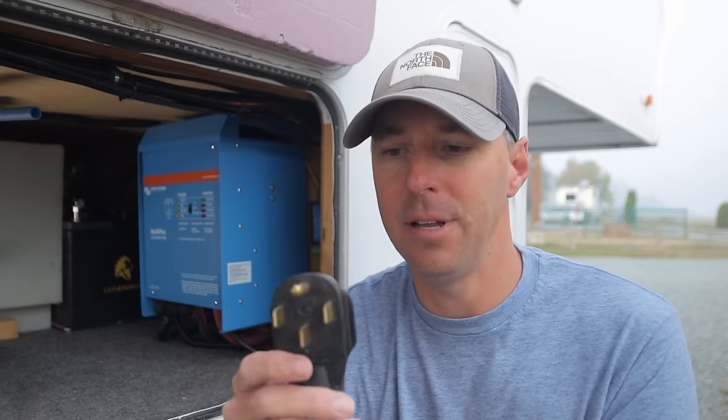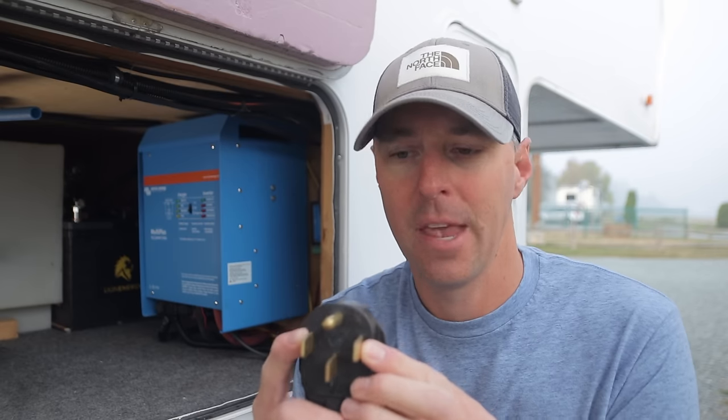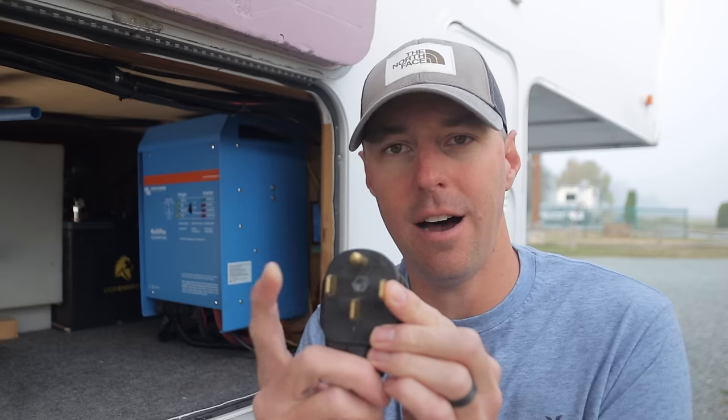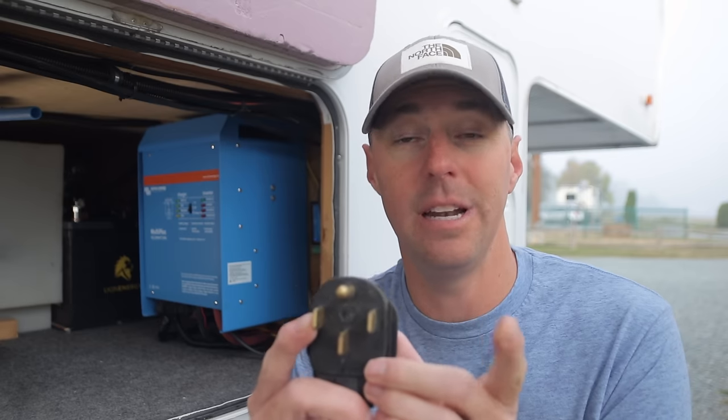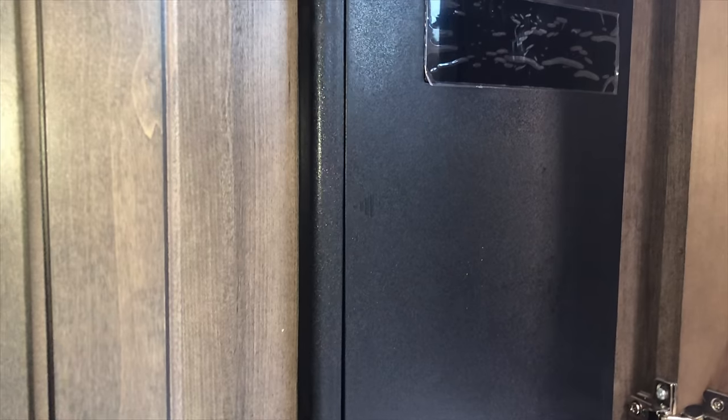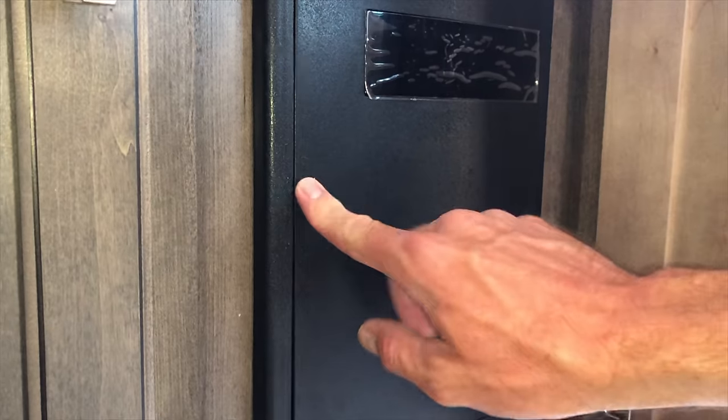Understanding the 50-amp RV: if we look at the end of a plug, we can see that there are four wires. You can describe this as a four-wire 240-volt single phase, or split phase — we have a hot leg on each side of the plug. We can have 50 amps on each side when plugged into a 50-amp service, giving you the potential of almost 100 amps.